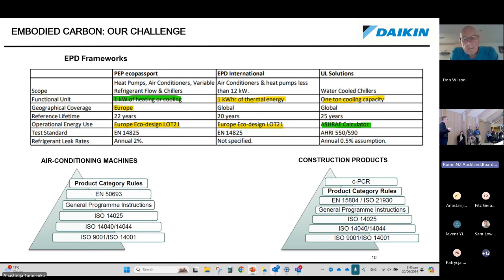So the seasonal performance data and bin profiles for when our units should be operational in cooling or heating, and what the efficiency is, isn't necessarily transferable for the region we sit in. EPD International also follows Europe, so that's a struggle, and it uses 1 kilowatt hour of thermal energy. But if you're sizing a heat pump, you size it on the cooling or heating requirement of the building rather than the electrical power draw, so it's not easily transferable for us.